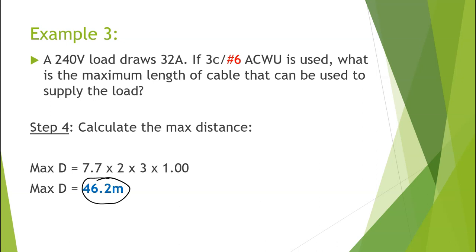And so a much more practical calculation is to use the voltage drop system in the CEC to determine the wire size that we would be running in order to have a circuit of a particular length carrying a particular current. Now, because this is not the way that the system is set up within the CEC, we have to manipulate the system a little bit and approach it in a fairly unique way.